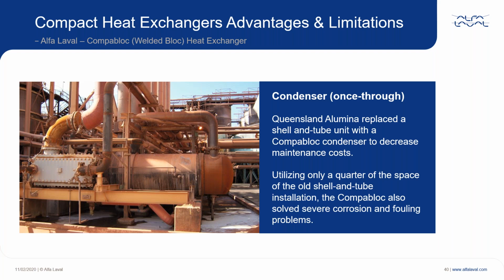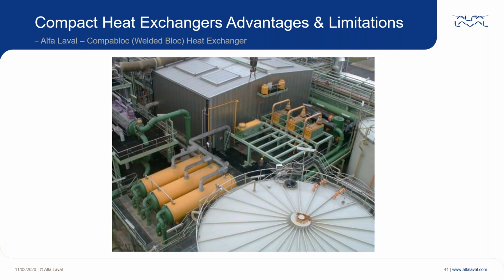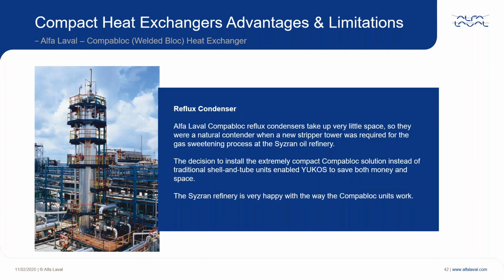Again, this is a copper block installed in Australia at an aluminium plant. The Compabloc is smaller. It does the same duty as the shell and tube behind it. It uses less materials. And again, another comparison. With this one, you've got the 3 Compablocs on the back do the same performance as the three shell and tubes at the front. The customer was a little bit apprehensive, hence he's got the 4th Compabloc there as a standby. And again, you probably won't be able to see it on this slide, but at the top of that column, there's a small reflux condenser.